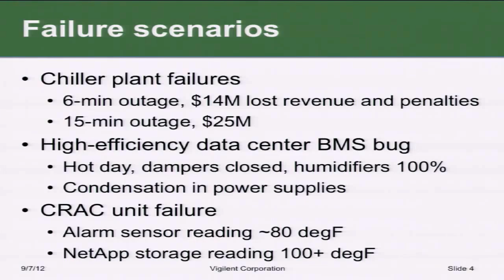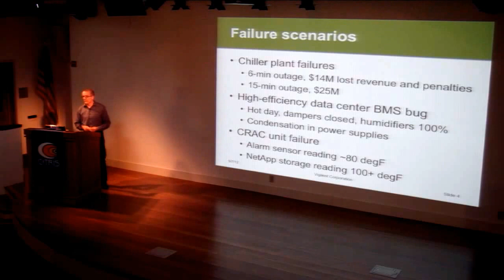Here's an example where they had a single air conditioner failure. They had sensors in the data center that would read temperature and signal an alarm message to let someone know it's getting too hot. But because only one of them failed, the others were reading about 80 degrees and it didn't trip the alarm. It did cause the NetApp storage to get exposed to temperatures over 100 degrees Fahrenheit and shut down. These NetApp storage arrays are big and really important to the operation of one of these data centers. So even though this was a single air conditioner unit failure, it was an all-hands event, everybody who runs that data center was there fixing that problem at 3 o'clock in the morning. That is just not a fun event if you're running one of these facilities.